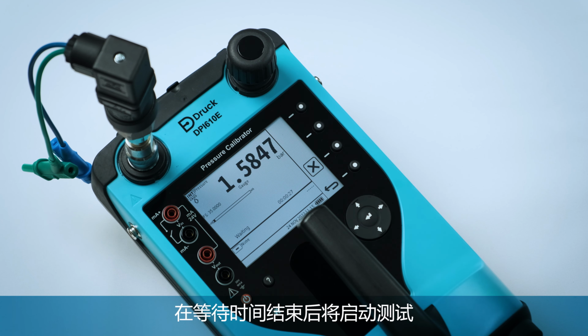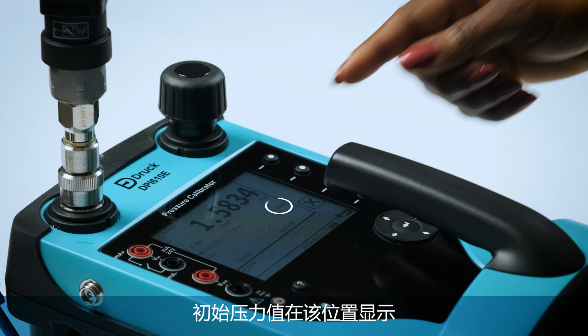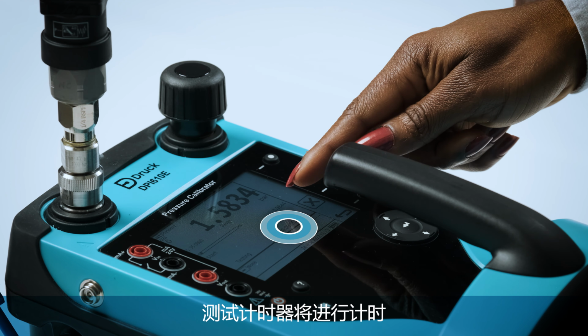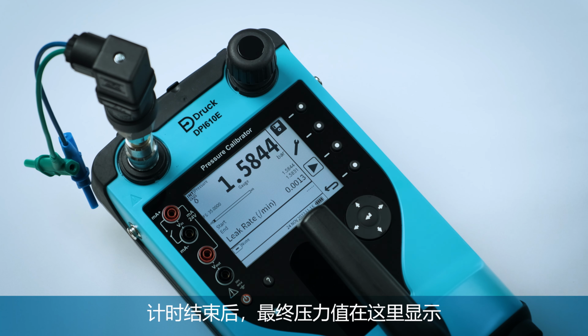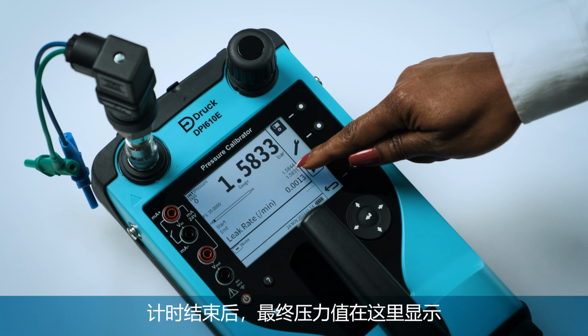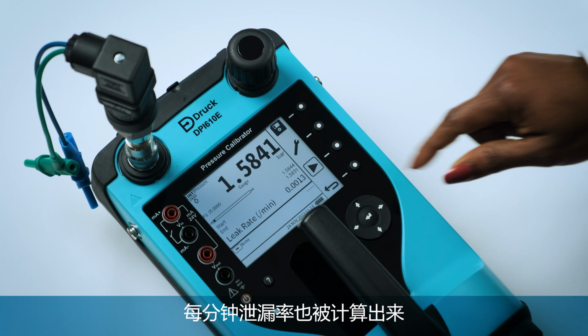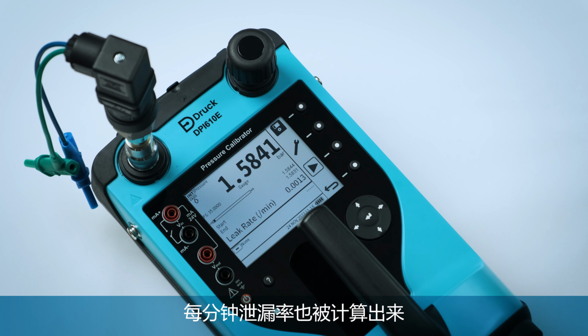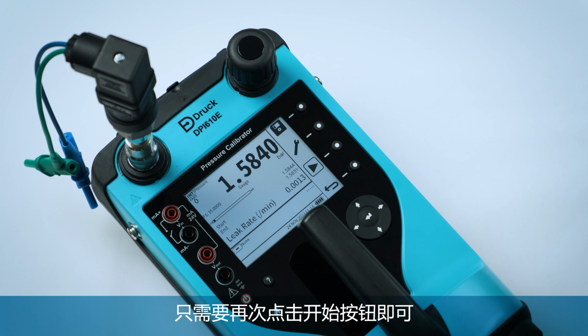The wait time will count down to 0 and the test will begin. The pressure at the start of the test is displayed and the timer for the test counts down to 0. Once completed, the end pressure is displayed and the leak rate is calculated and displayed as a rate per minute value. To repeat the test, simply press the play button again or exit.